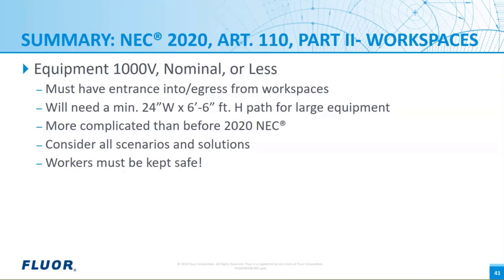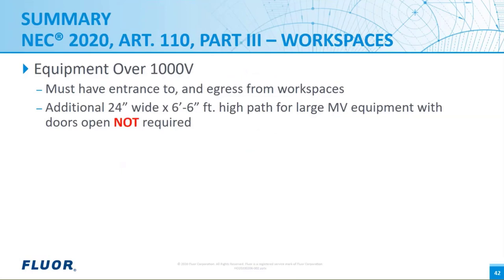But now you're going to need to maintain that 24-inch minimum width of this pathway with the equipment doors open only, again, where the equipment is rated less than 1,000 volts, greater than 1,200 amps, and over 6 feet in width. The 2020 NEC right now, as we speak, does not contain this same new provision for the 24-inch path with the doors open where the equipment is all greater than 1,000 volts. The reason that I'm saying as of right now today is because there may be a tentative interim amendment or a TIA that could be written in the next 2 to 3 years before the next cycle comes out. And if it's accepted by the NFPA Standards Council, then it will be part of the code.